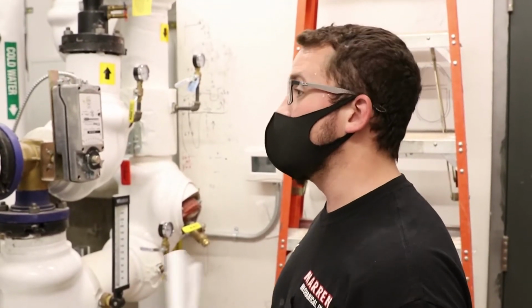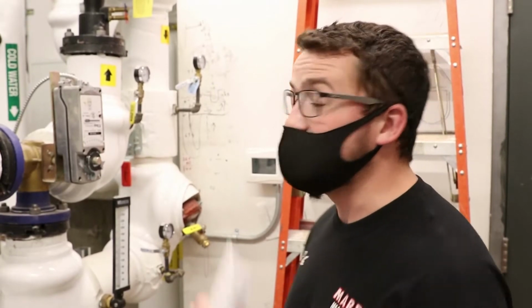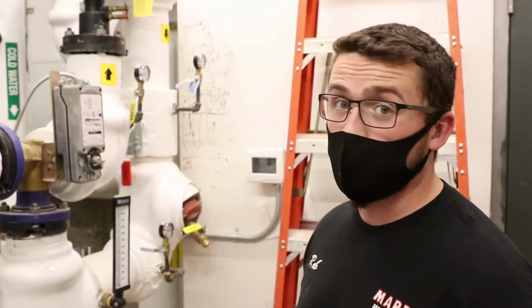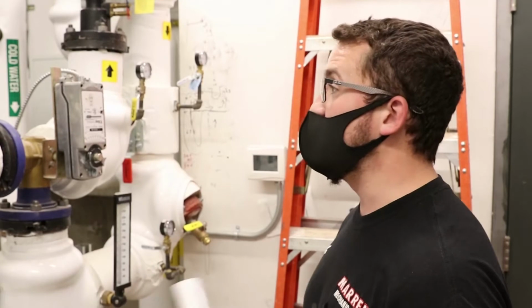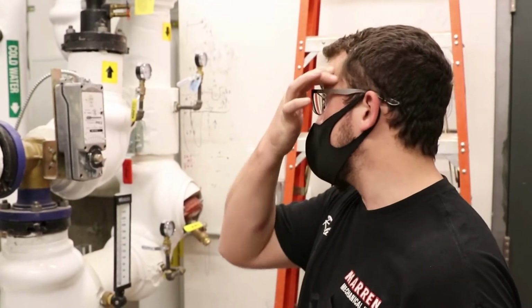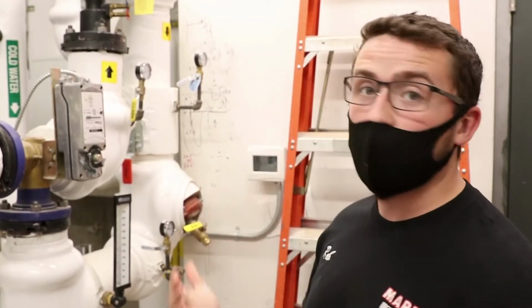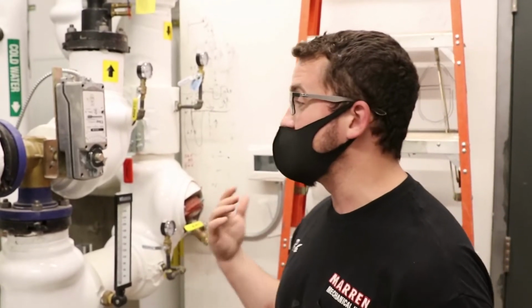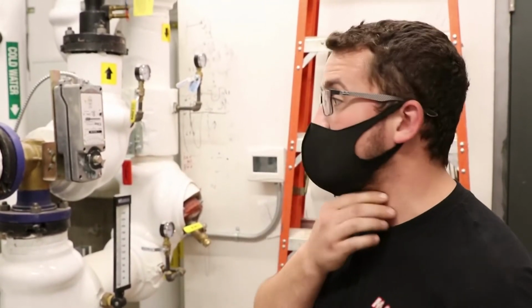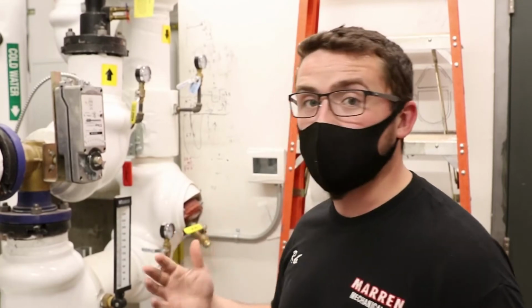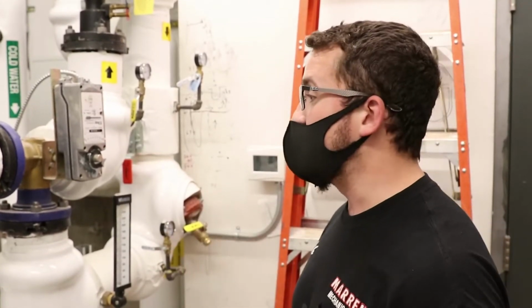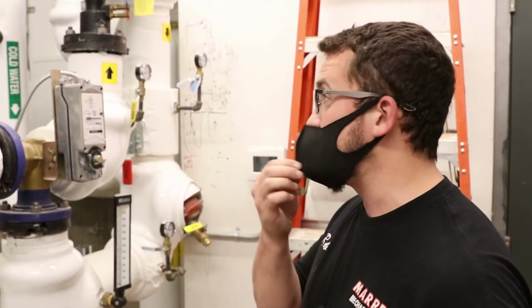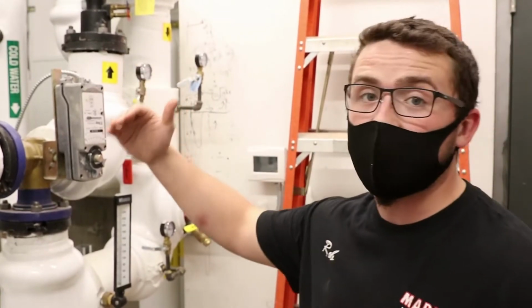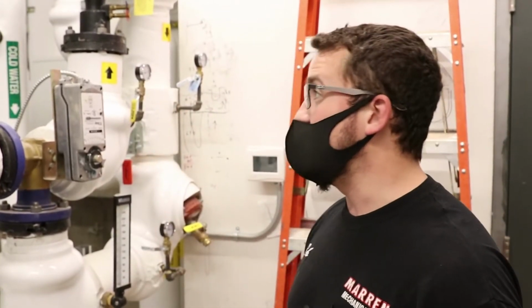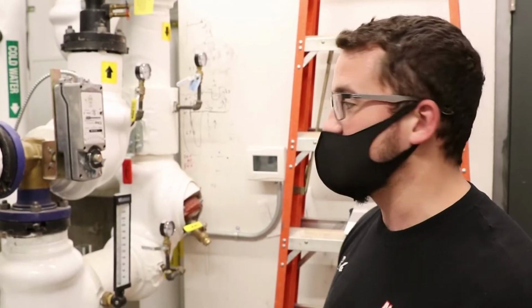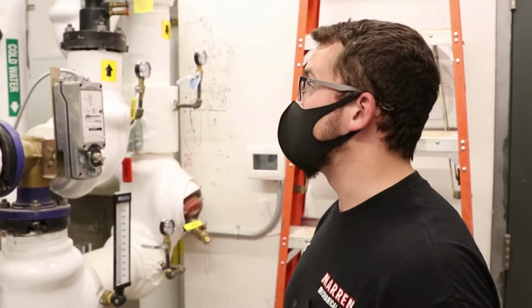The best way, if you're having an issue with this and you need to clean those, you would look for poor performance. If this water heater, over time, begins to struggle more and more with making temperature, or eventually is not capable of reaching temperature anymore, you should call for service to troubleshoot and rule out other issues. But at that time, if there are no other issues, it may become necessary to flush out the inside of the tank and clean either the inside of the tank or the heat exchanger, which can be done by a service company.